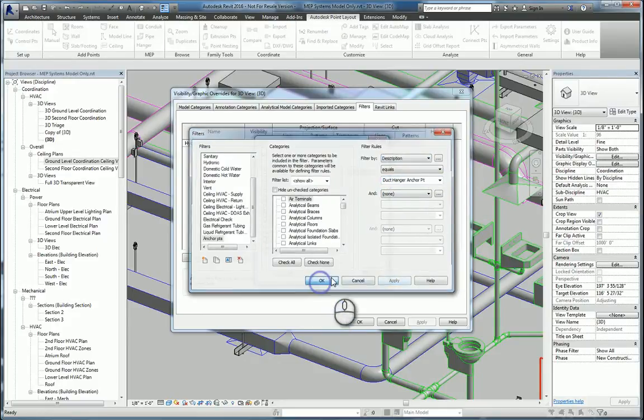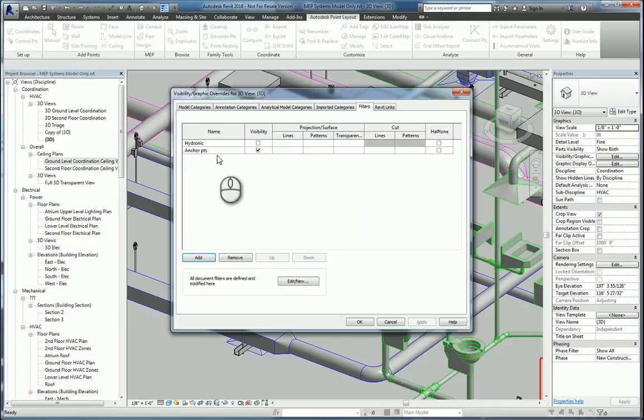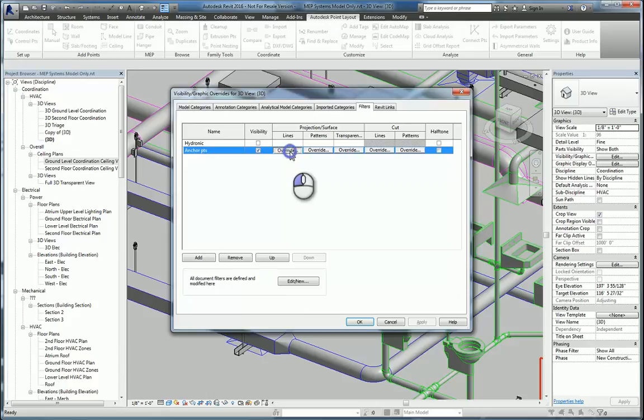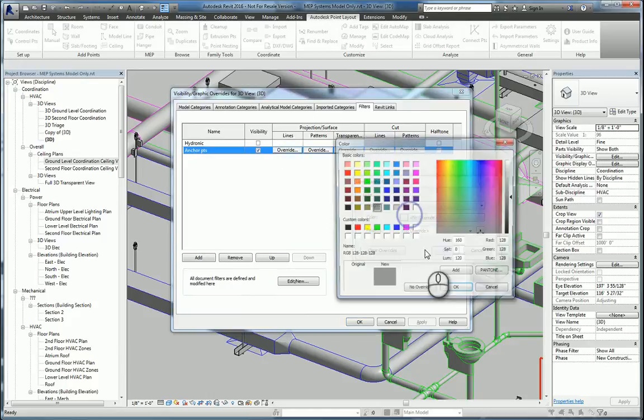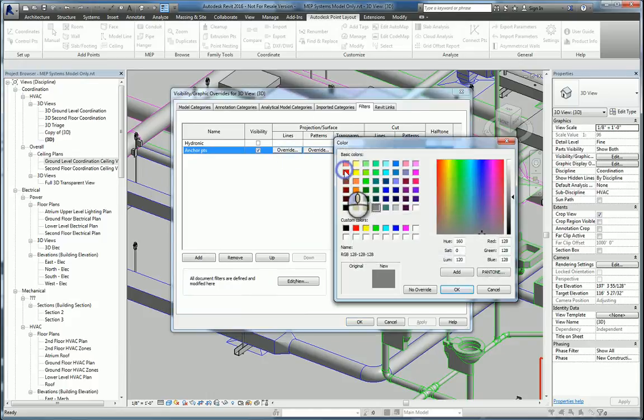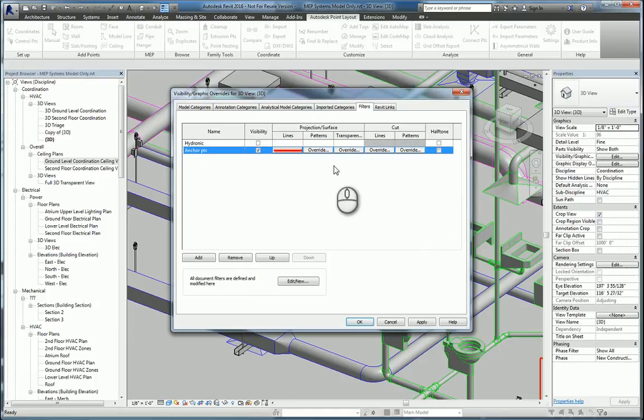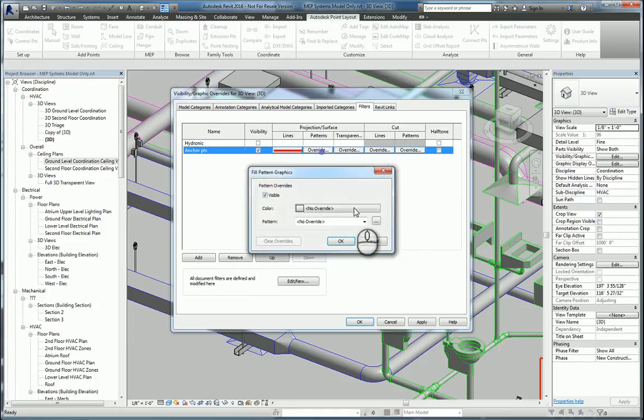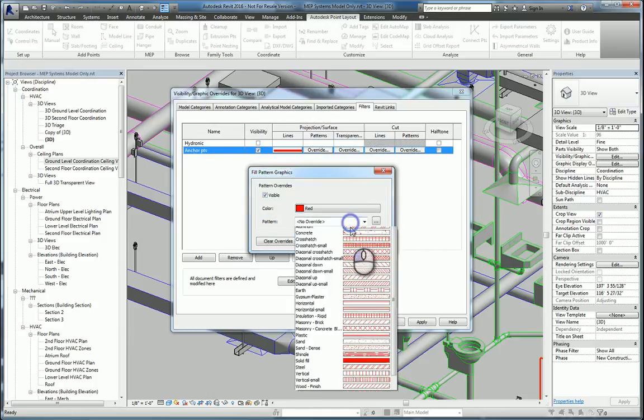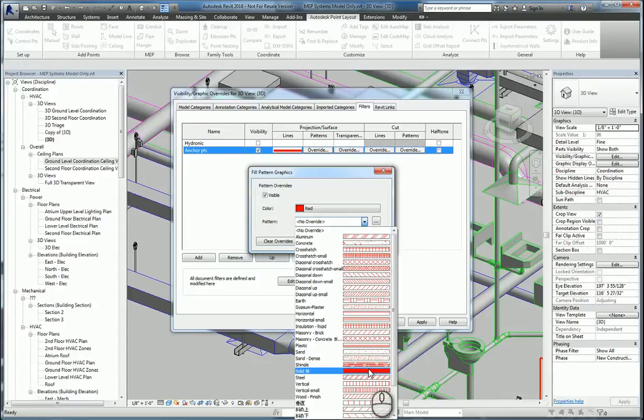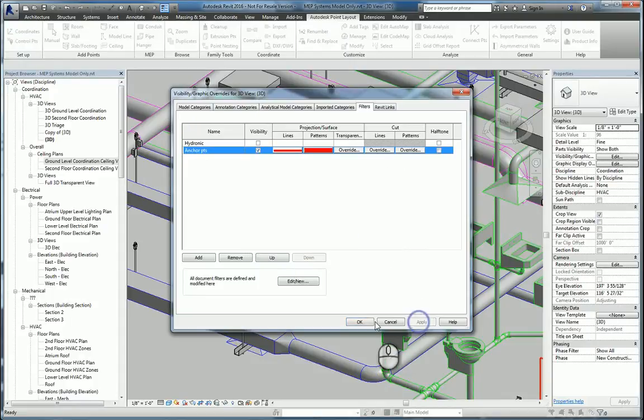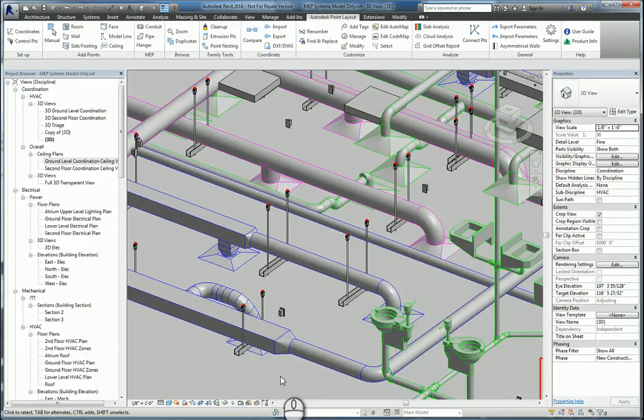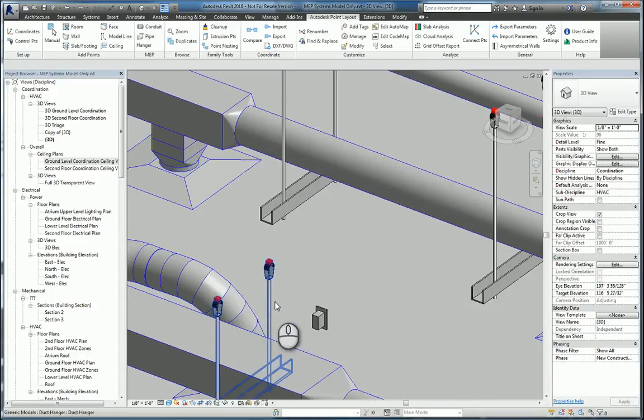And we want that filter condition to be the description has to equal that Duct Hanger point. Now that that has been created, we can highlight it, select it. It's there. It's visible. We can change the line work to be whatever weight that we want, whatever color that we want, as well as the pattern. And we'll make that the same color, and we'll make it a solid color. Now that we've done this, you can very easily see in red those anchor points.